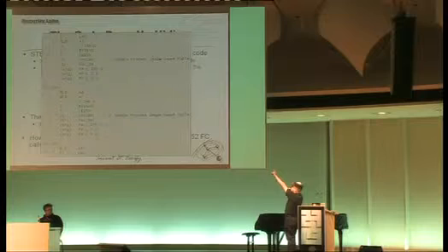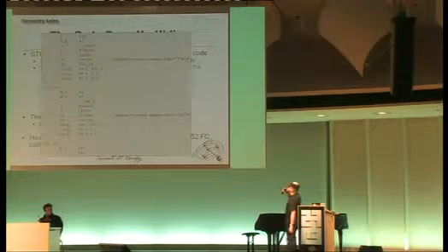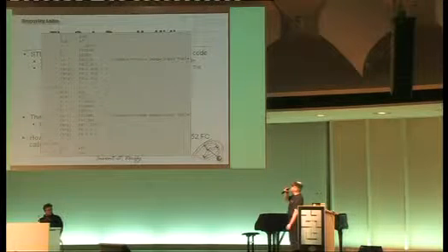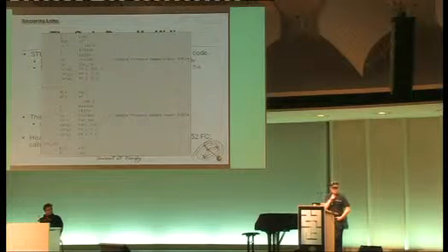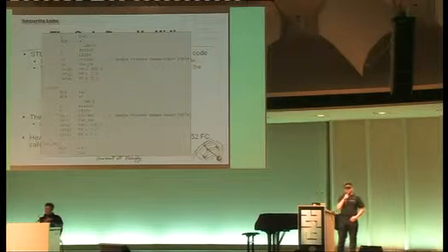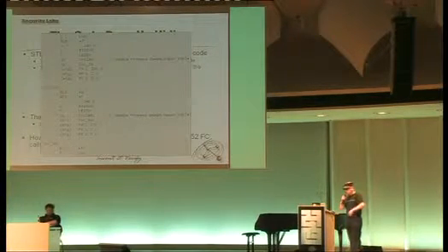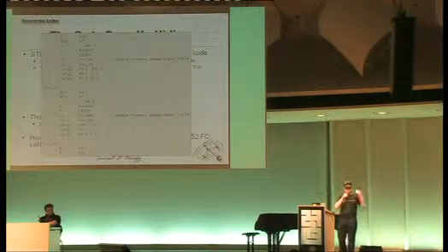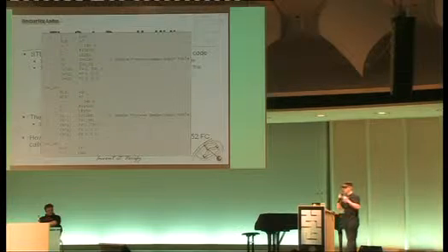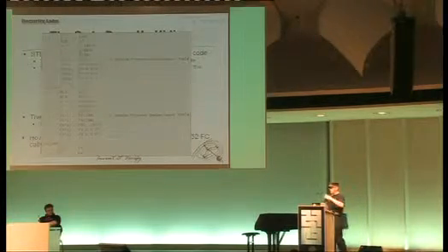There's two calls essentially that they made to update the process image input and output tables manually, which is pretty smart actually, because they're disconnecting the PLC from the normal scan cycle. They disable the automatic updating of the inputs and outputs and do it by hand in order to modify what the PLC thinks is on the inputs and outputs.